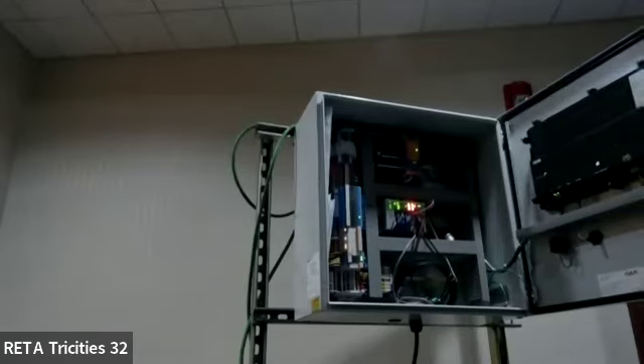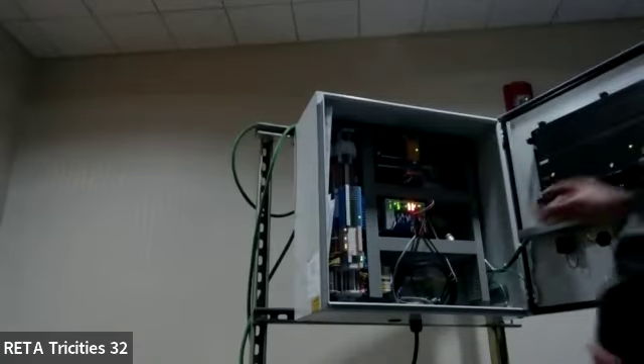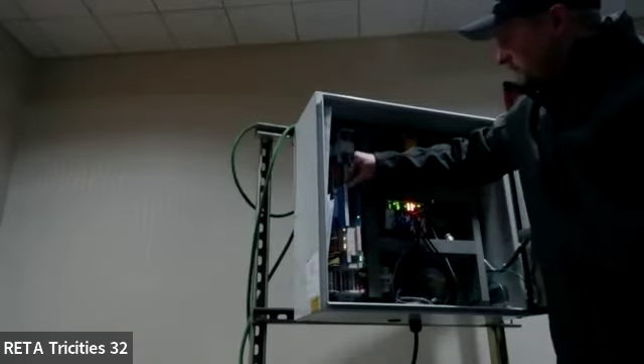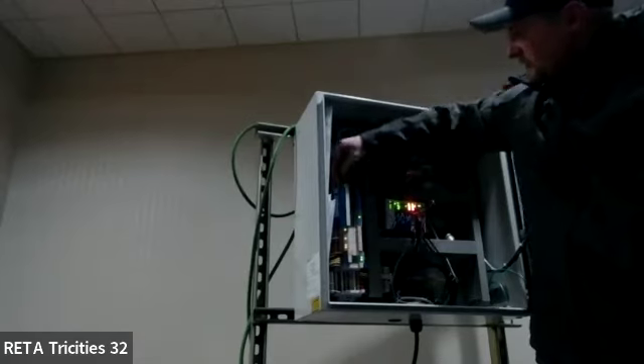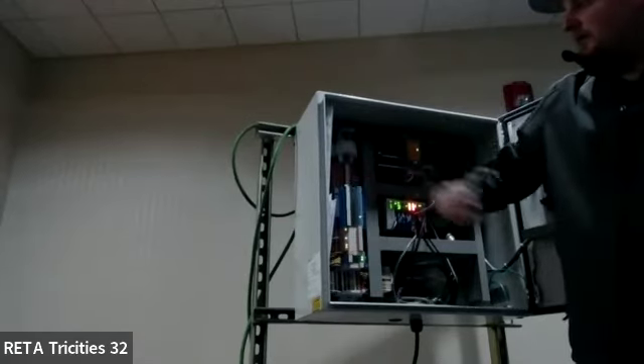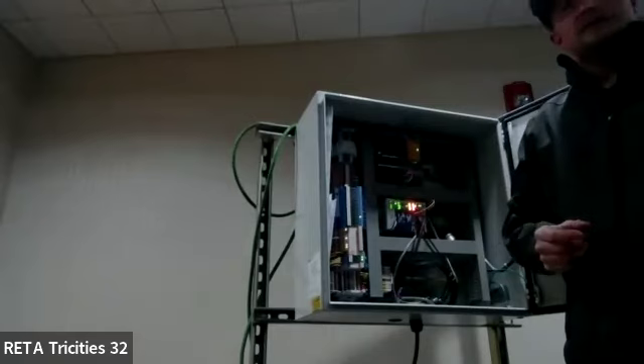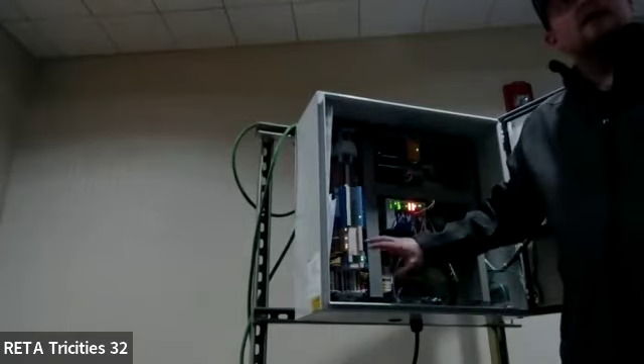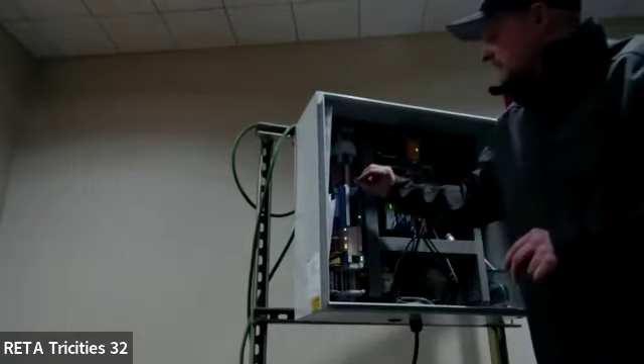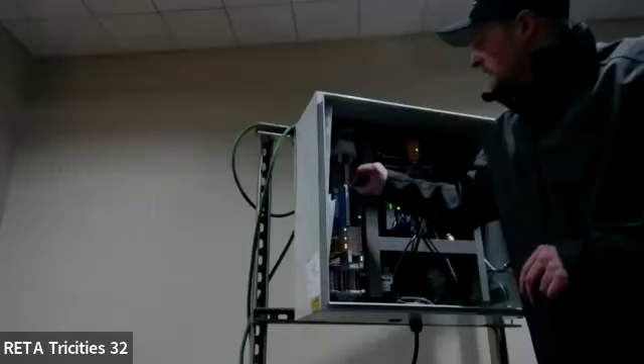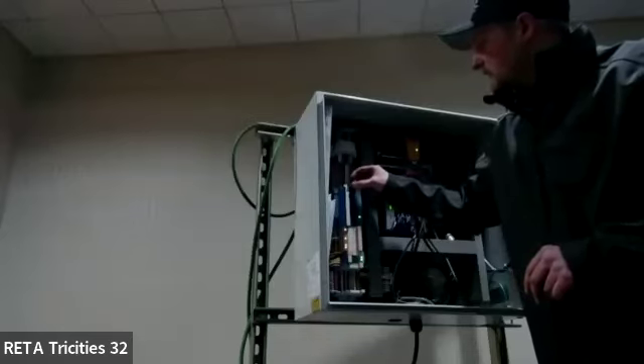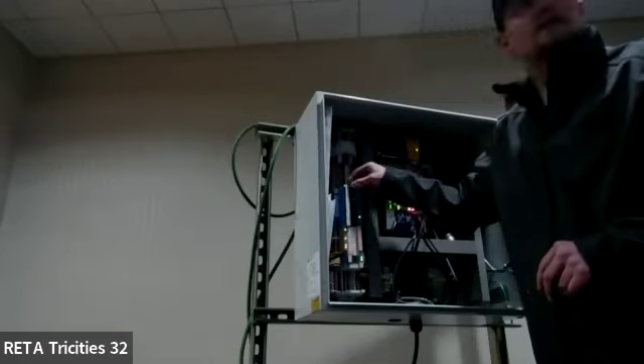Can you show how to pop out the little relays in case you have to change them? Yeah, so you'll just press this, like 5CR right here, to the side. And it'll pop out. This is an output module. The black ones are outputs, the whites are inputs. So if you've got one that doesn't have any wires landed on it, you can steal it out of there and put it in the one in the back.